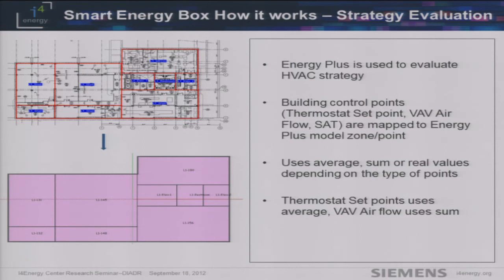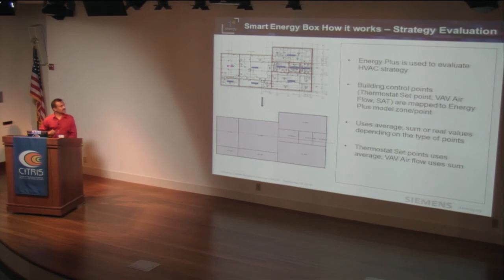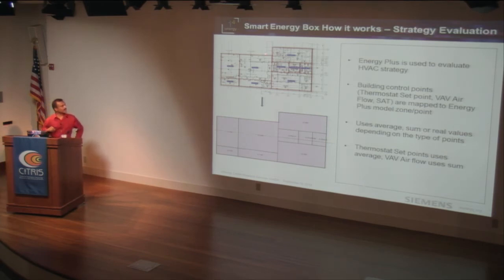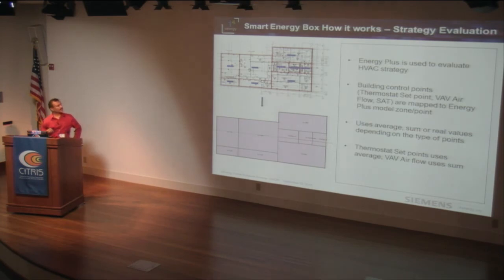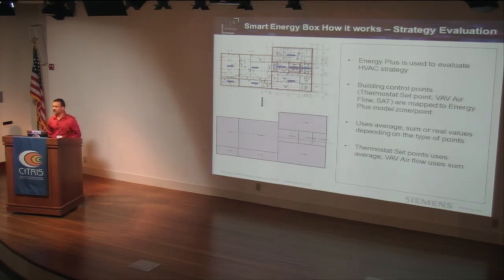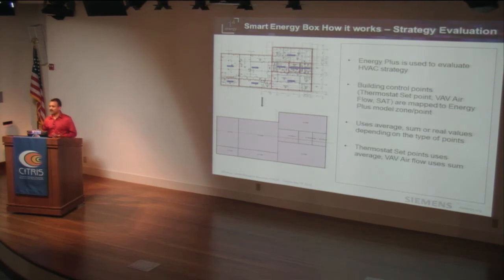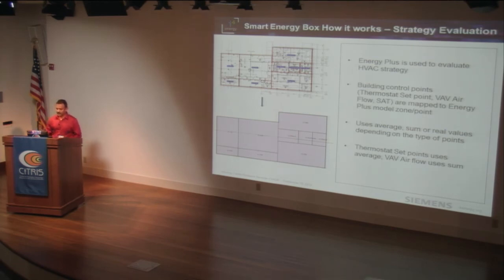For strategy evaluation, we use EnergyPlus. This is a real building model developed by LBNL for this project. In the real building there are many control points, which in the model may be clubbed into one zone. For example, thermostats distributed throughout the building might map to a single zone in EnergyPlus. We take all thermostat set points configured as part of the strategy, compute the average for temperature set points or the sum for VAV air flows, and adapt them for the corresponding EnergyPlus model for evaluation — this is how LBNL performs strategy evaluation.